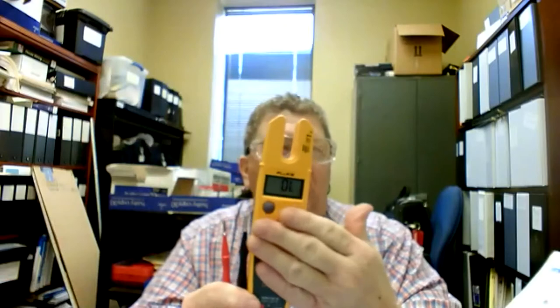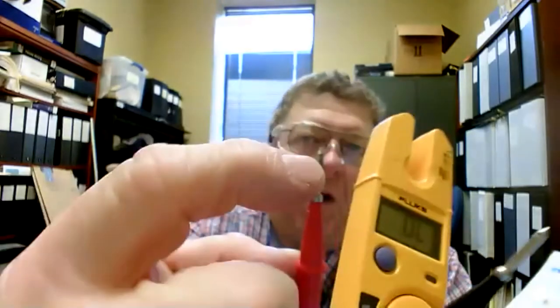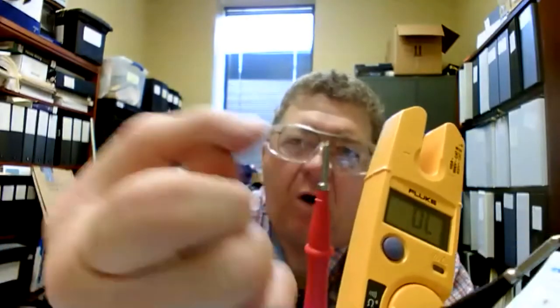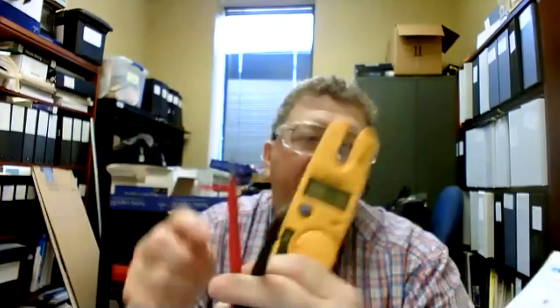Well, if you take that battery voltage and you come in contact with a receptacle when you're sitting on ohms here, then what you've done is you put battery voltage in here head-to-head with AC voltage, and it's gonna collide, okay? It's not going to be good. You're just going to go pow. I've actually seen it blow out a hunk of the probe here. I've actually seen it arc so bad that it blasted a part of the metal off of the probe, and I had to replace the probe.